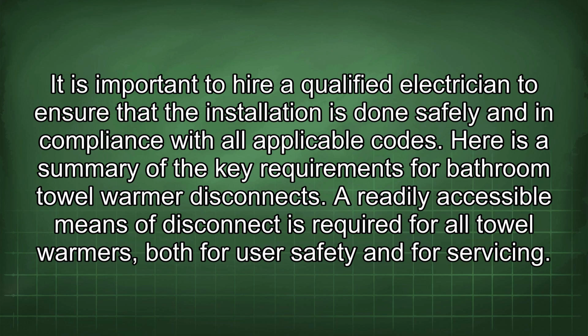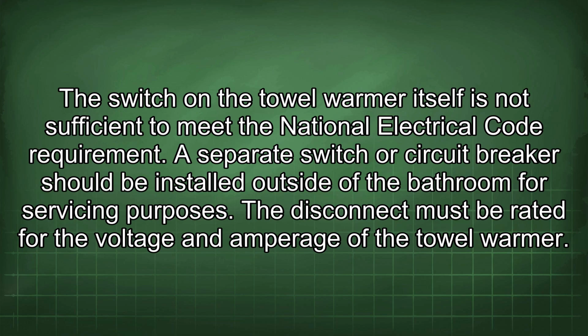Here is a summary of the key requirements for bathroom towel warmer disconnect. A readily accessible means of disconnect is required for all towel warmers, both for user safety and for servicing. The switch on the towel warmer itself is not sufficient to meet the National Electrical Code requirement.